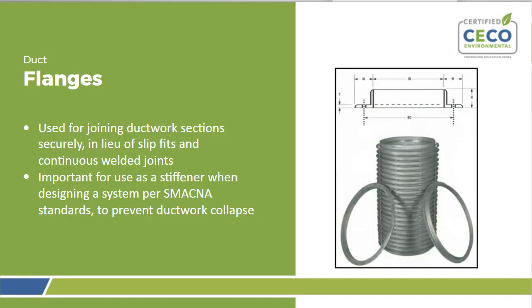Flanges. We use flanges in industrial systems almost always. The only time we ever do without flanges is if it's a material that could possibly leak, where they want it welded, but flanges are needed. They help you join the systems or the sections of duct together in lieu of using a slip fit, big and small in connection like you would have in HVAC, or a continuously welded joint that I mentioned.